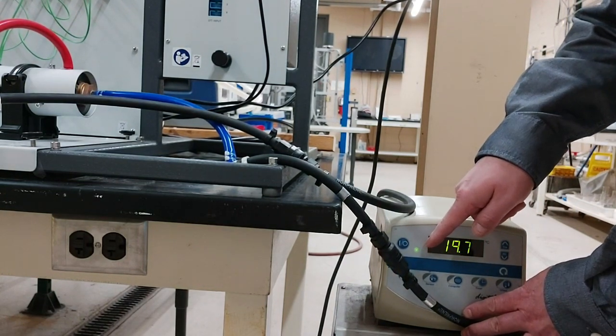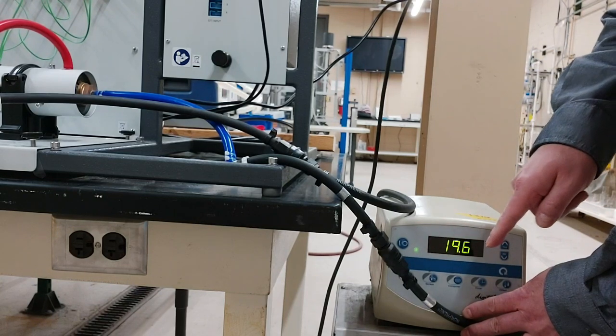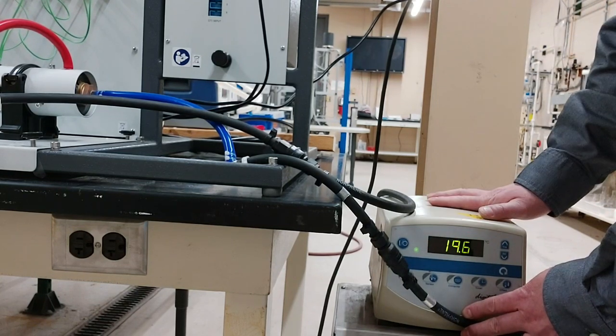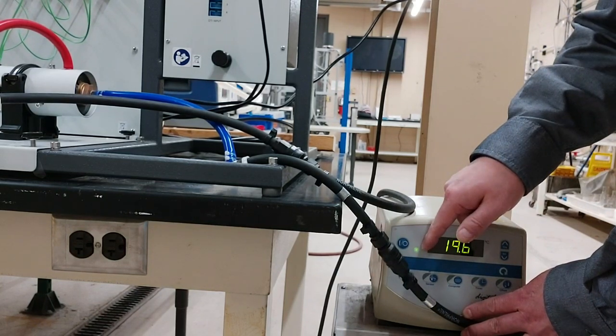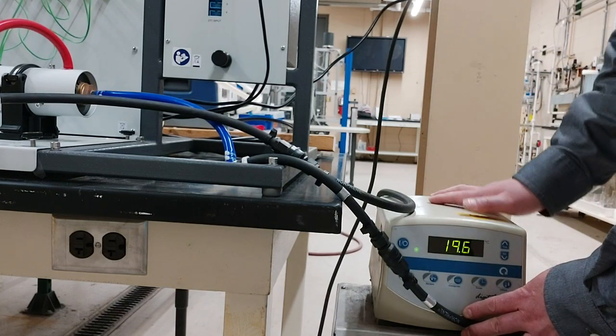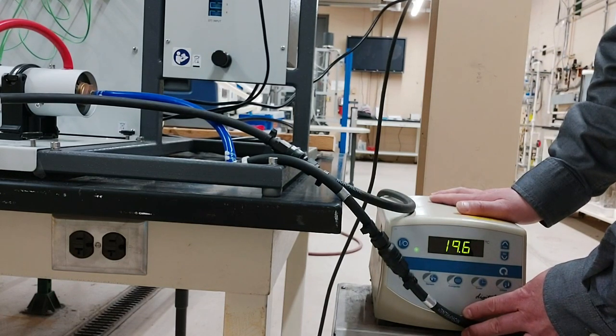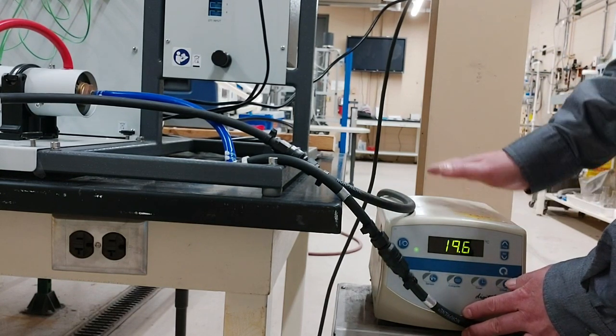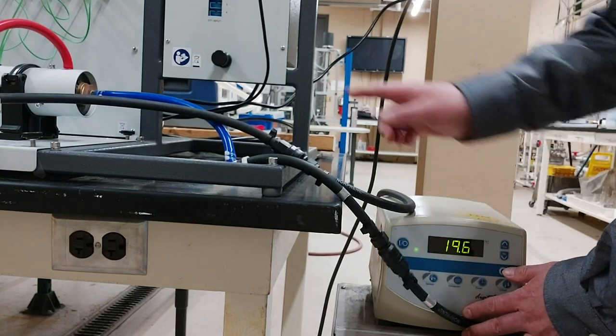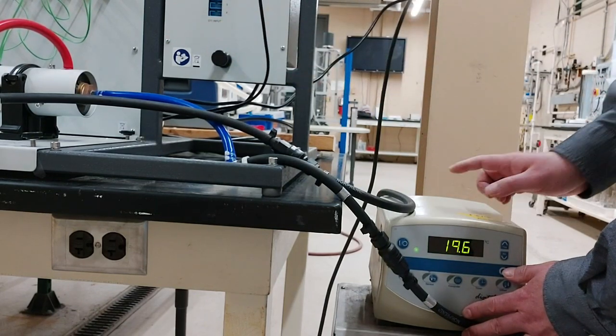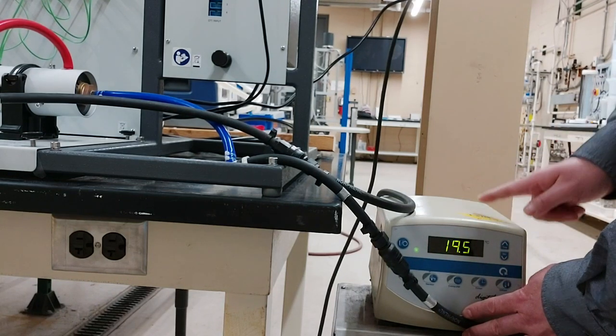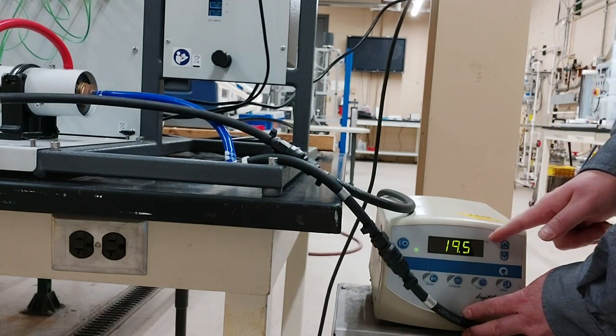When this green ice crystal LED light is on, the chiller is in the cooling mode. This recirculating chiller can actually do both cooling and heating to maintain the desired temperature. But for this experiment, it's receiving heat from the instrument's heated sample, so it should be primarily operating in the chiller mode during the experiment.